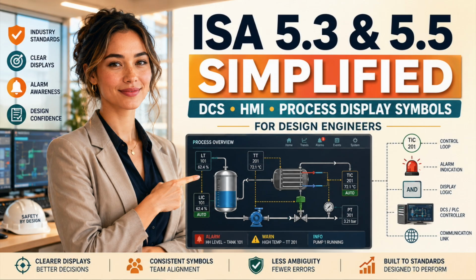Display hierarchy is equally important because not every screen should carry the same amount of detail. The highest level overview should tell the operator whether the plant is healthy, which area is abnormal, where production is constrained, and which major equipment is unavailable. The process area display should explain major flows, equipment relationships, key measurements, and significant control loops.